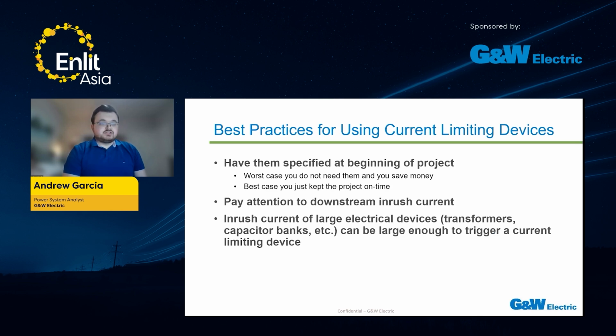You do want to pay attention to downstream inrush current. That's very important, as downstream inrush current would be indistinguishable from a fault to a lot of these current limiting devices and could end up triggering them. So you need to keep that in mind when you're determining which kind of current limiting device to use, or even if you can use current limiting devices. Just to emphasize that again, the inrush current of large electrical devices, such as transformers and capacitor banks, can be large enough to trigger a current limiting device.